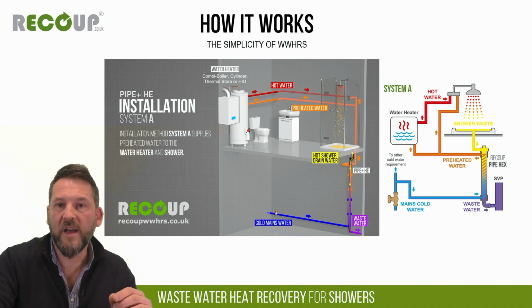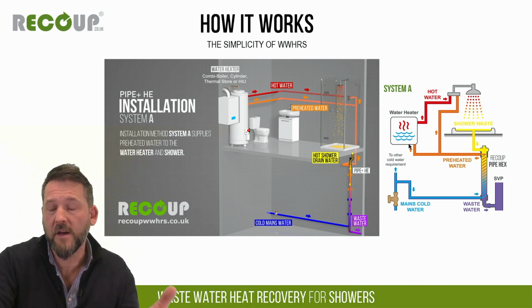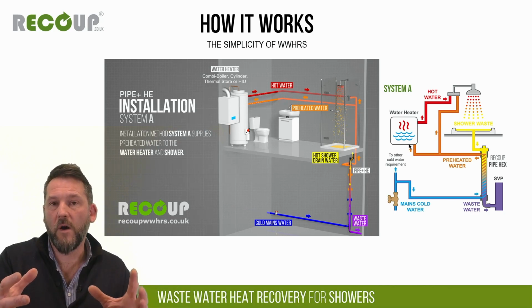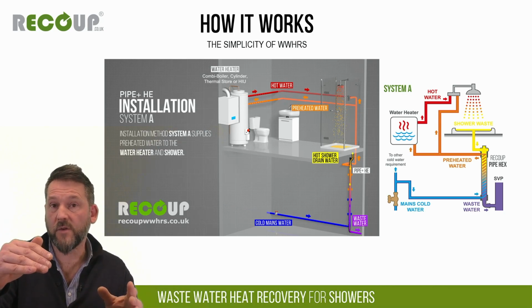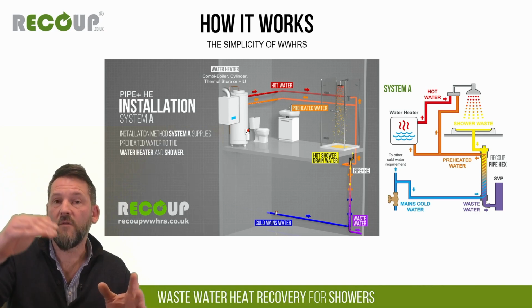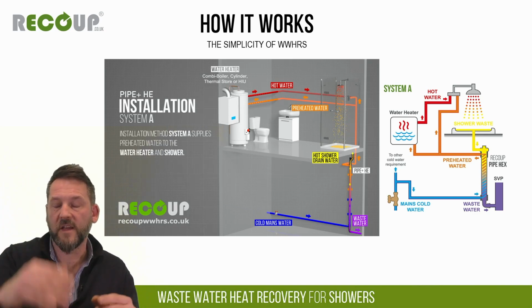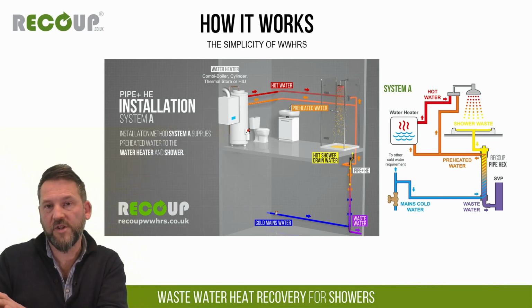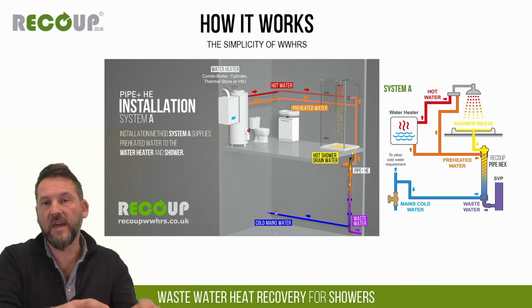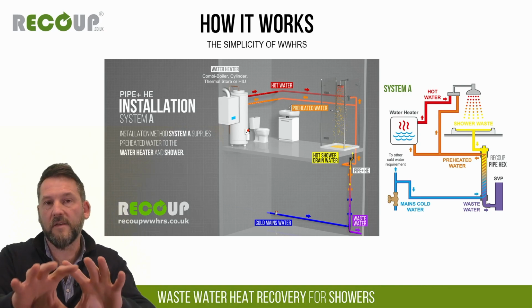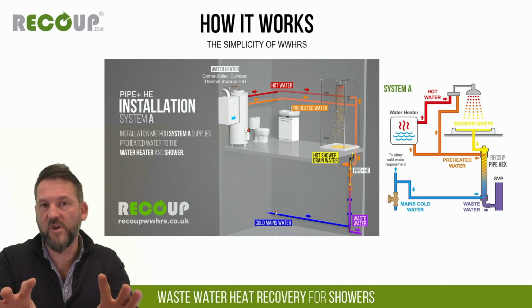And then also by sending the preheat back to the hot water source, so in this case a cylinder, the cylinder now only has to work to heat from about 25 or 28 degrees up to 60, rather than heating from 10 degrees up to 60. So we're using less hot water per shower, and the hot water we are using is being produced more efficiently. So that's System A, and that's the setup that we would normally expect on a primary shower in a new build dwelling, for example.